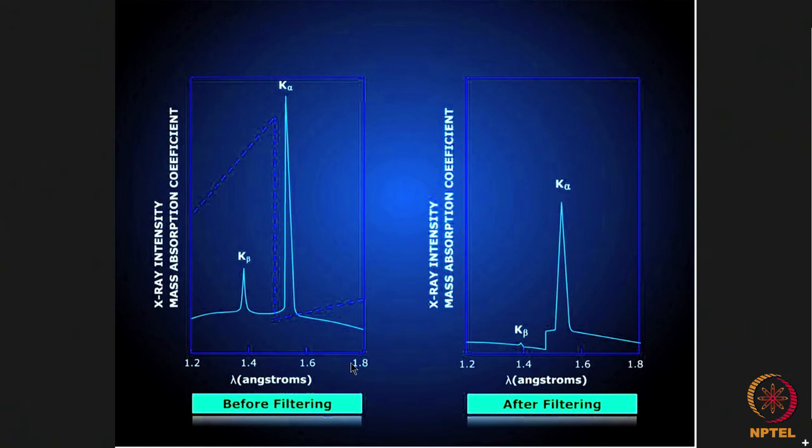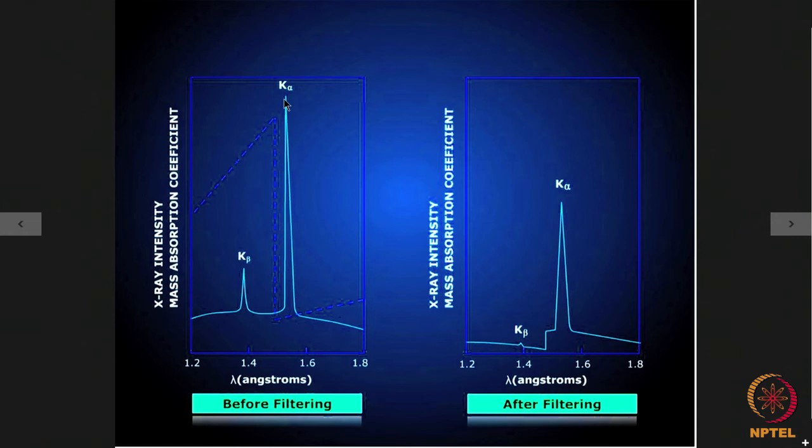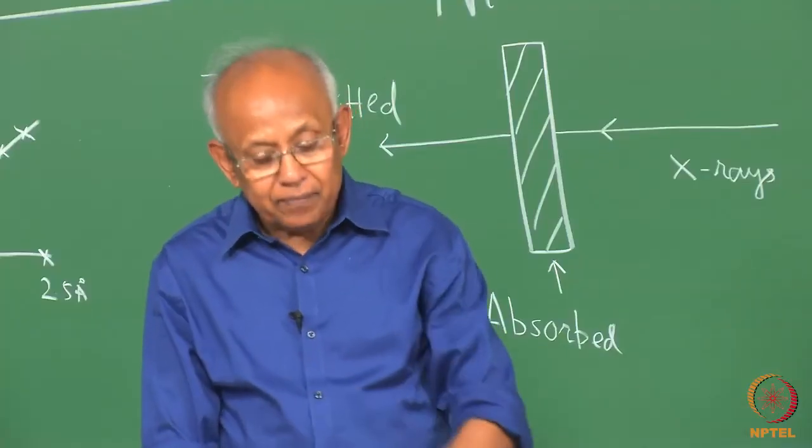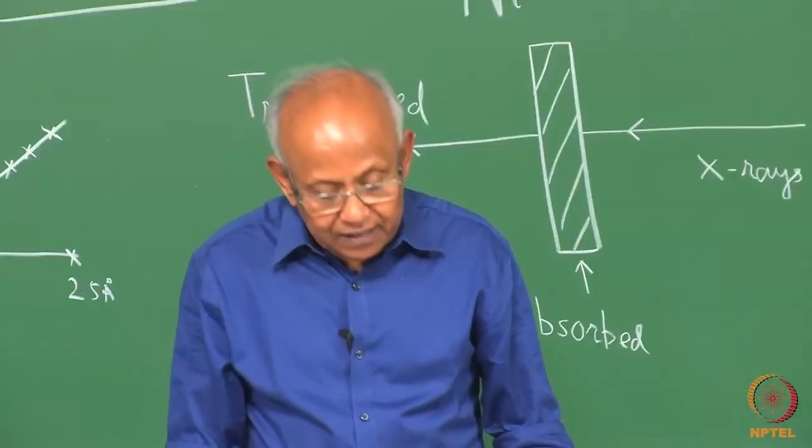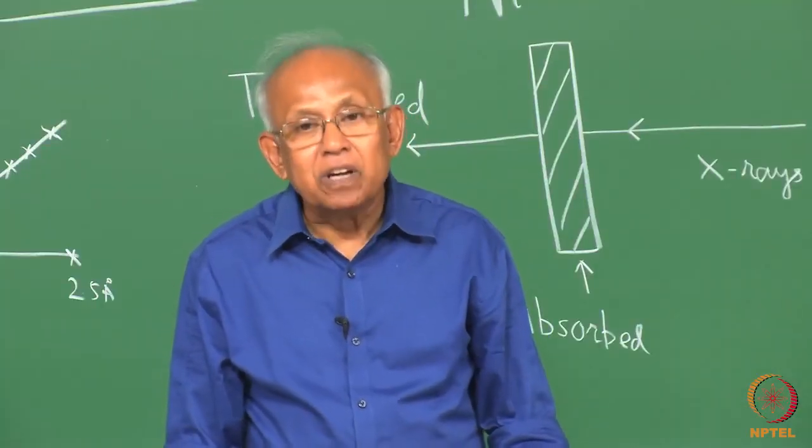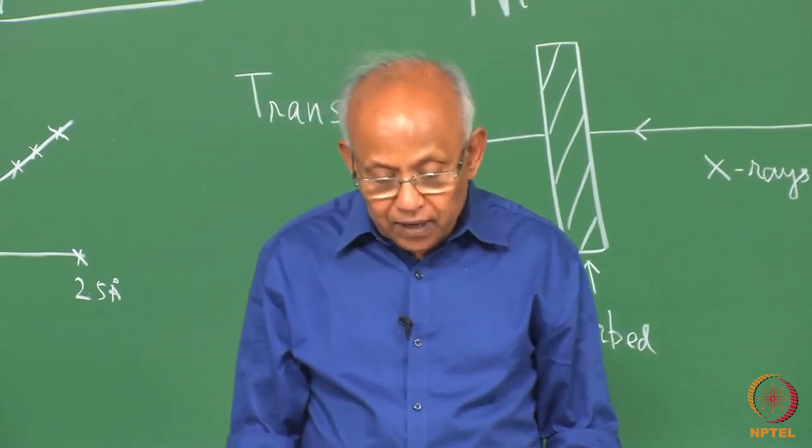What does that mean? That if we use nickel in front of the radiation coming out of a copper target in an X-ray machine, most of the radiations other than K-alpha will be absorbed to a much higher degree than the K-alpha radiation itself. In other words, the output of the X-ray machine when it goes through a nickel filter will be containing mostly the K-alpha radiation along with lower intensities of K-beta and other white radiation components. Nickel can be used as a filter in case of an X-ray machine having copper as a target material.